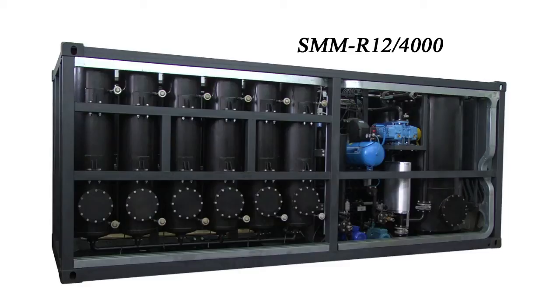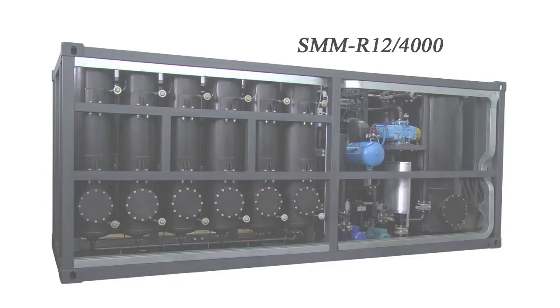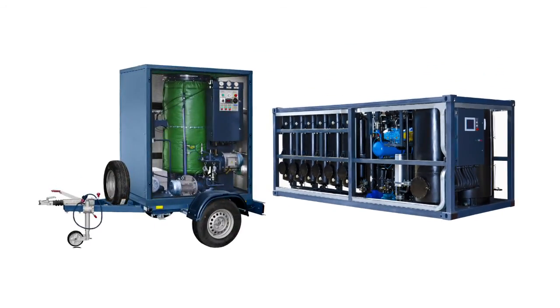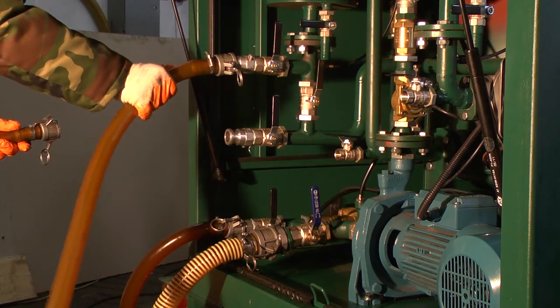The sorbent in the system can be reactivated up to 300 times, which constitutes one and a half to two years of operation until it needs to be replaced. The replacement process is simple — the sorbent is reactivated one last time and unloaded from the columns in dry state. Waste sorbent is environmentally inert and can be disposed of as construction site waste or household waste. The system can be operated as a standalone application for oil regeneration in oil facilities, but can also be coupled with a degasser, connected to a special bypass line.